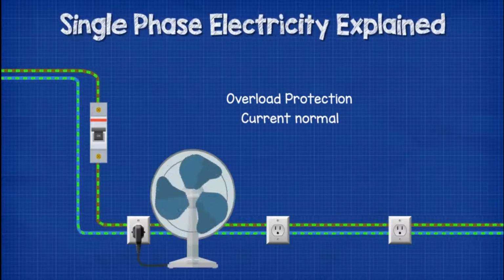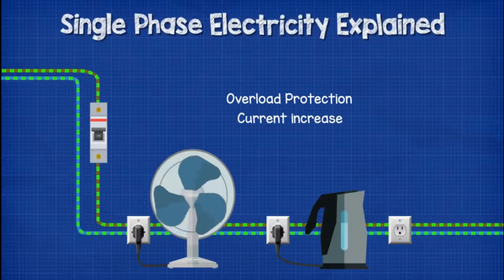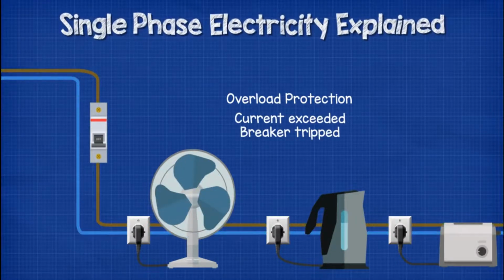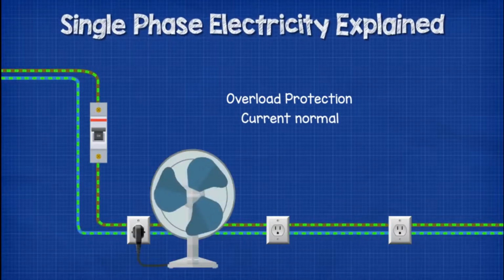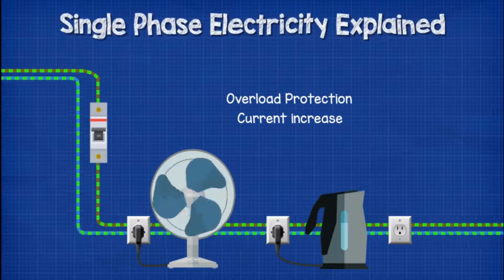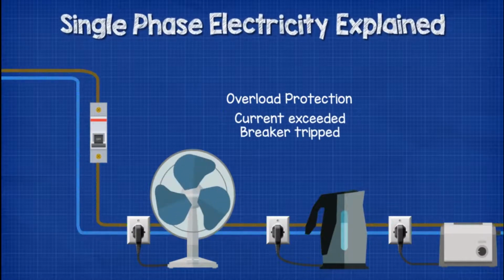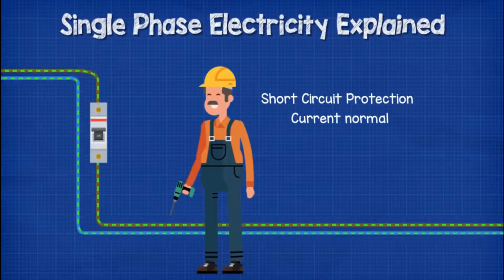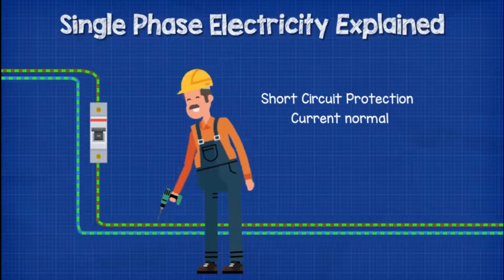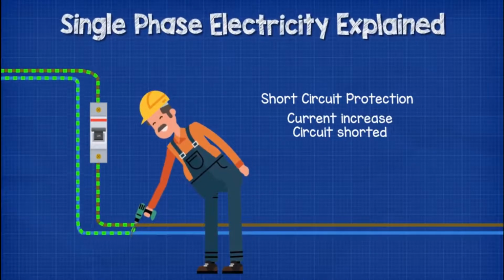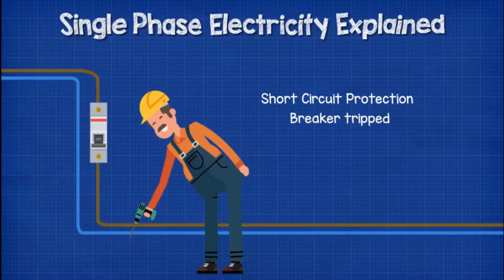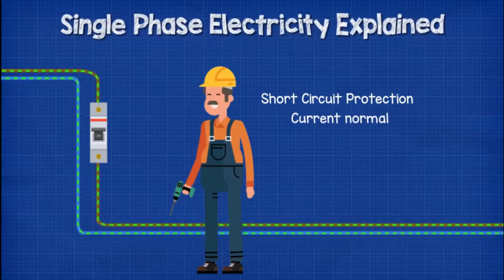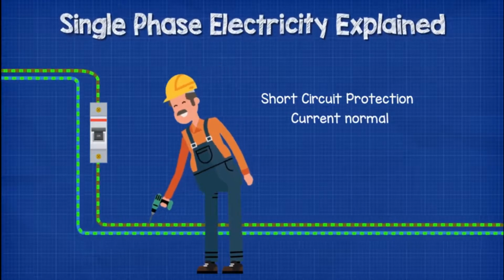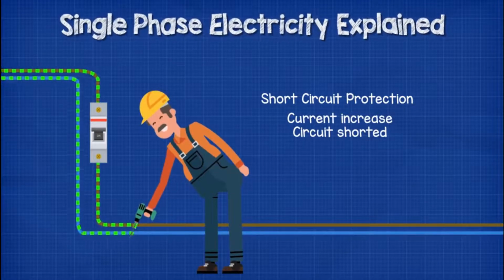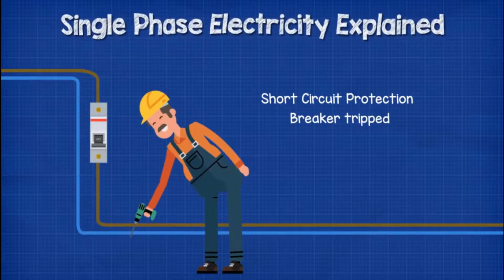If this value is exceeded on that circuit, for example by gradually plugging in too many things, then the MCB will trip and cut the power to protect itself. The other protection it offers is short circuit protection. In the event of a short circuit, for example the live touches the neutral, then the circuit is bypassed and there may be a large and instantaneous increase in current. This will create a magnetic field inside the MCB which will cut the power to protect itself.